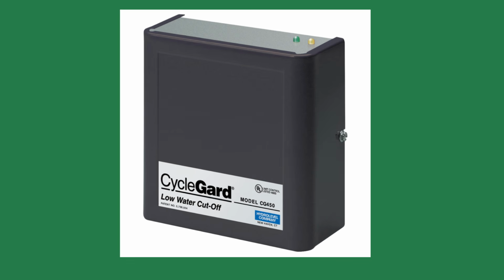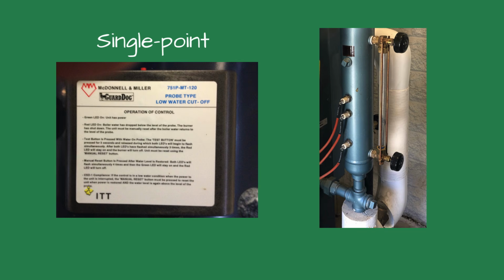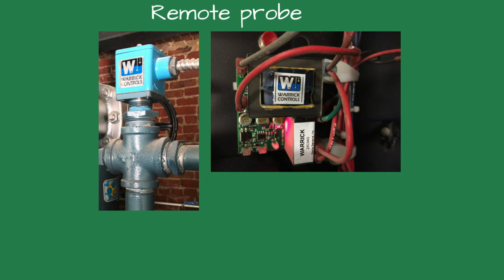Many low water cutoff controls include a short time delay, usually 10 to 30 seconds, to avoid nuisance trips from temporary splashing or minor water level fluctuations. Some controls are single point, just for the low water cutoff, while others use multiple probes at different heights for combined functions like low water cutoff, water feeder or pump control to add makeup water, and high water alarm. One advantage is that the probe can be installed in a different location than the control itself.